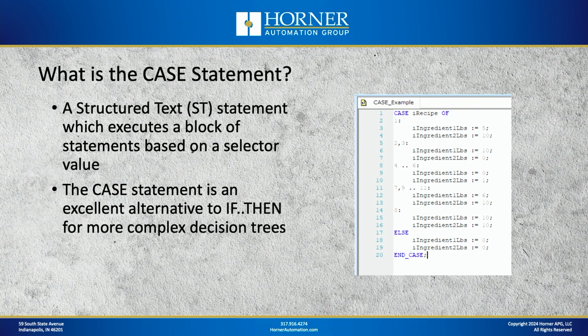Well, it's a structured text statement which executes a block of statements based on a selector value. Now, if all you need to do is execute statements based on one or the other value, then the if then else is probably the way to go. It's a statement we're all familiar with, we use very regularly, and for handling a couple different conditions, it's a good way to go. However, if your decision tree is a little more complicated than that, if there's more cases, if you will, then the case statement is something you should evaluate. So that's what we're going to do today.